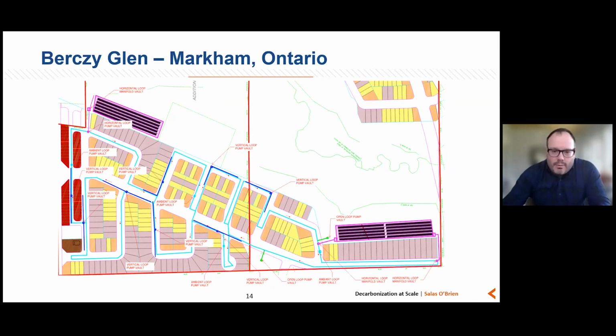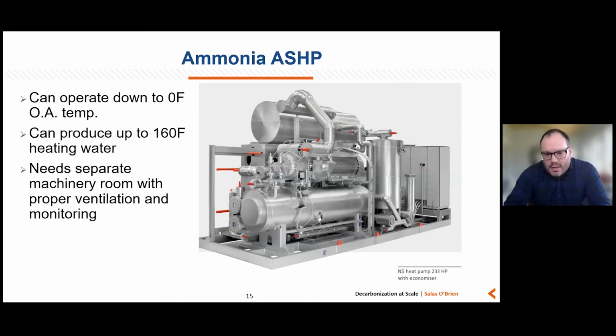And the last topic I really want to touch on is air source heat pumps. I think our previous speakers certainly spoke to how cost constraining the ground source heat pump strategies can be, and that's very true. They can be difficult from an affordability perspective. Air source heat pumps do offer really good alternatives, even at scale. You have to look beyond the typical technologies here. Here I'm showing an ammonia air source heat pump, which has its operational issues, certainly, and you need to be careful about operating ammonia systems, but it can operate down to 0 degrees Fahrenheit and produce water up to 160 degrees Fahrenheit. So if you're looking for a higher temperature solution that can minimize your building conversion costs, this kind of technology can be utilized, and certainly Johnson Controls, Daikin, and Multi-Stack are all looking at producing systems like this, just to name a few manufacturers.